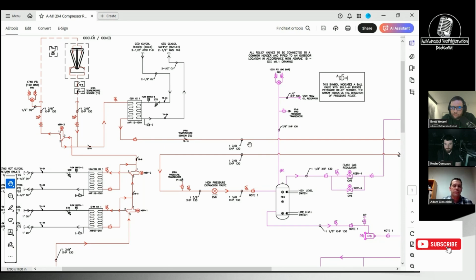But before I move on, one of the negative sides of that, you do have to be a little bit careful with that because the receiver size is really critical. If you've got your drop leg coming down at 60 degrees and now you boost this high pressure expansion valve to say 1200, what you normally operate in subcritical would be a 3-degree subcooling right here. Now you've added 400 pounds to the operation of this valve. It's easy to get 30 or 40 degrees of subcooling right here. The downside of that is it does make the rack run efficient, but you have to have enough volume in the receiver then to flood and fill the condenser or the gas cooler.